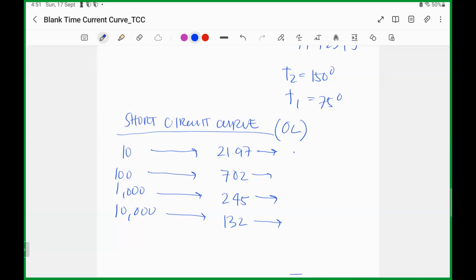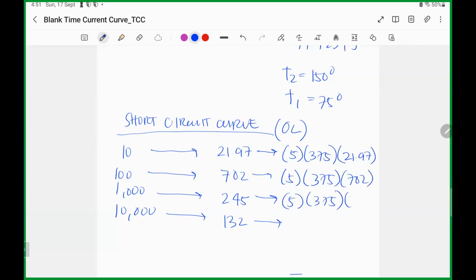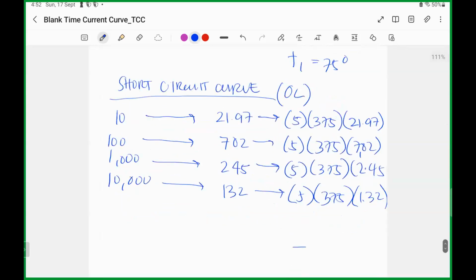So now, para makita mo yung overload, for example, nung cable 1, the ampacity of cable 1 or THWN 250 mm square based sa PEC at 75 degrees table, it is 375. Since naka 5 sets ka, mas tataas yung ampacity mo. Then you should multiply this by 21.97 at 10 seconds. 5 times 375 at 702, 5 times 375 at 245, so 2.45, this is 7.02. And 5 times 375 multiplied by, what is last one? 132%, 1.32. Okay, so this one will be the overload curve of your 250 mm square cable.